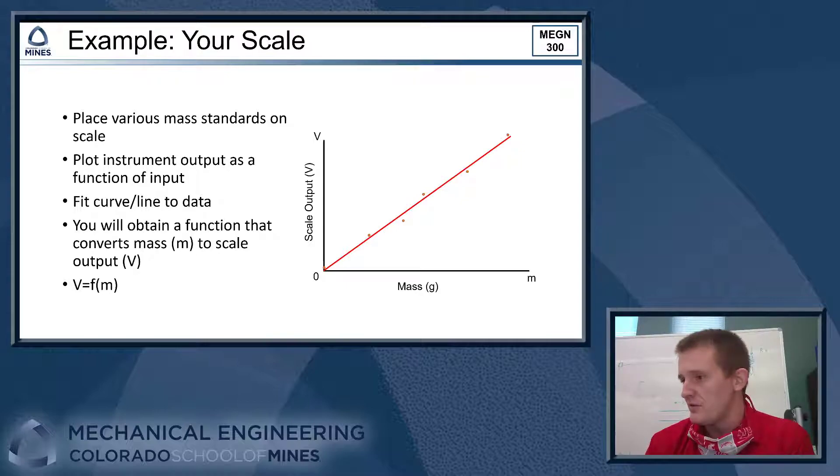Okay, so the way that we're going to go about actually doing this for your scale is we want to get various mass standards. So we have a bunch of these calibrated laboratory weights that you can use. We also have some digital scales that you can weigh whatever items you have around the lab and use those as standards. Also, we just need some sort of well-characterized, we know that this mass weighs this many grams that you can place on your scale and use that as a standard. So what you want to do is find various ones, and we'll plot the instrument's output as a function of input. So in this case, I'm using volts. Some of you guys might have frequency as your scale response. That's okay, you just have frequency on the y-axis instead of volts. And we're going to plot a bunch of points, and we should obtain some sort of function that converts mass to a scale output. Or like volts in this case here. So that's your function that you start off with.